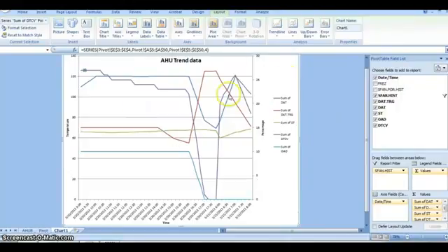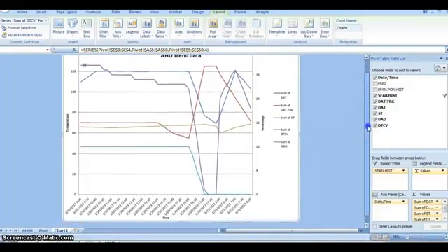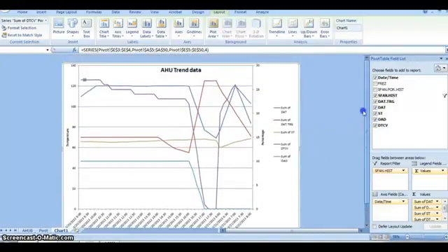So this is a great example of how a school should function. And the good thing about trend data is you can trend tons of data. You can trend up to months at a time, weeks at a time. It doesn't matter how you want to trend your data, and you just look for logical errors in the system when the supply fan shouldn't be running. If the cooling valves are running during late nights, such as like 12 at midnight on a weekend. You just look for logical errors. So that's how you trend data. And thank you for your time.